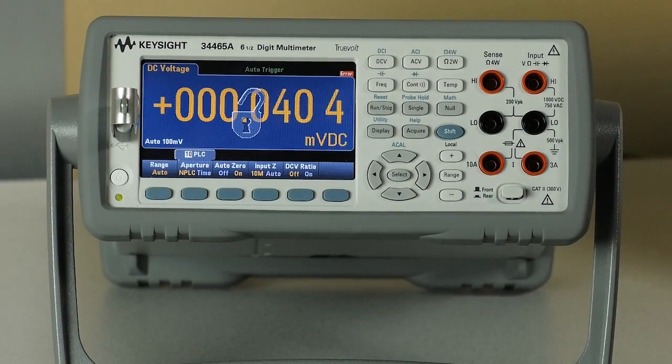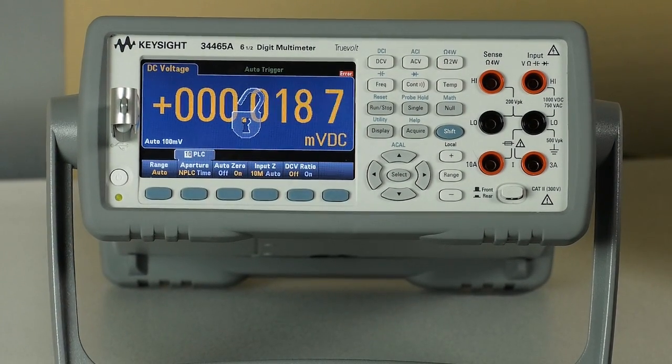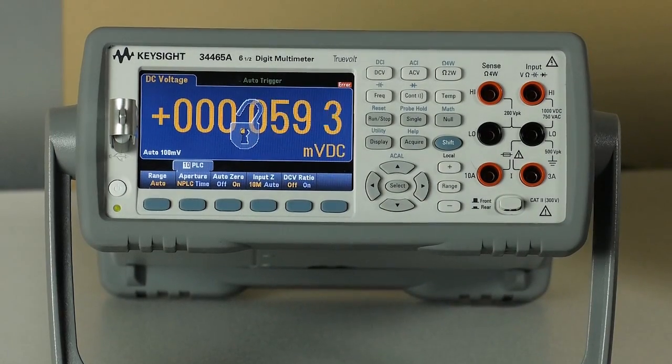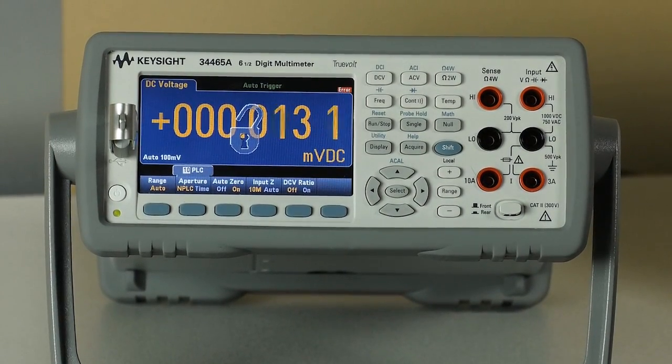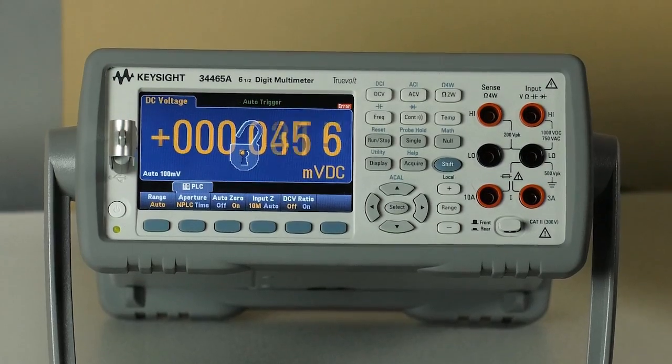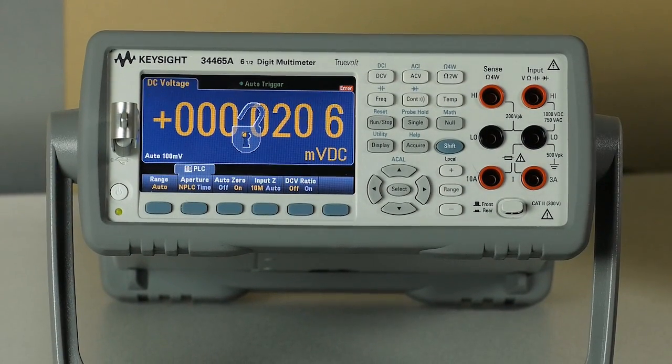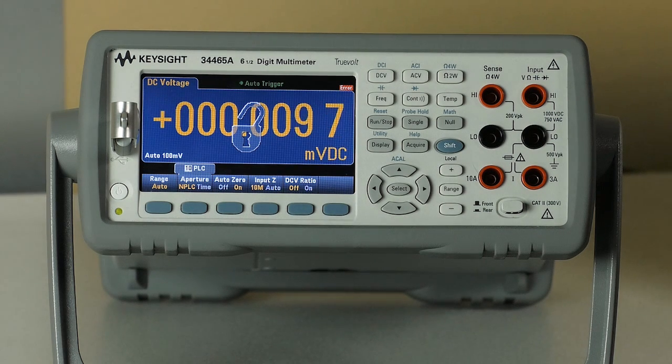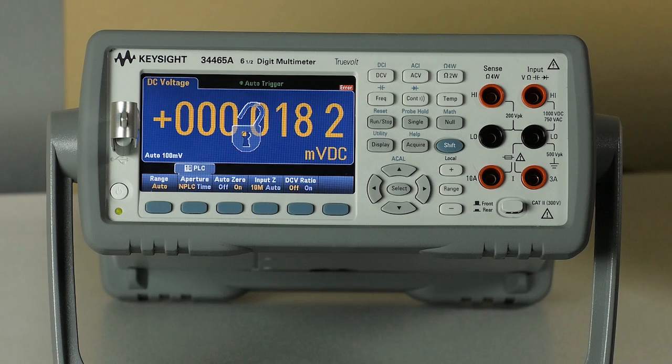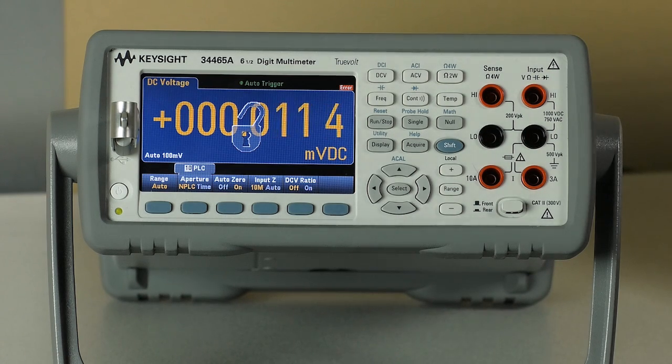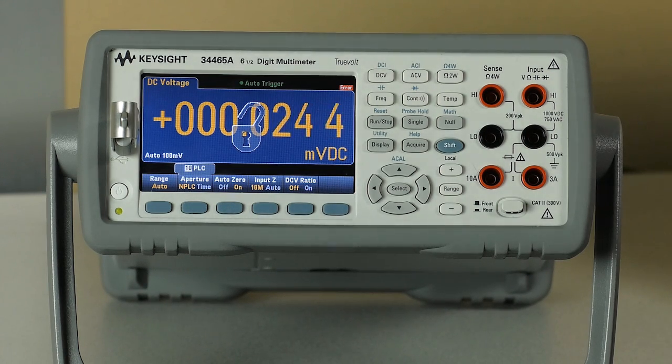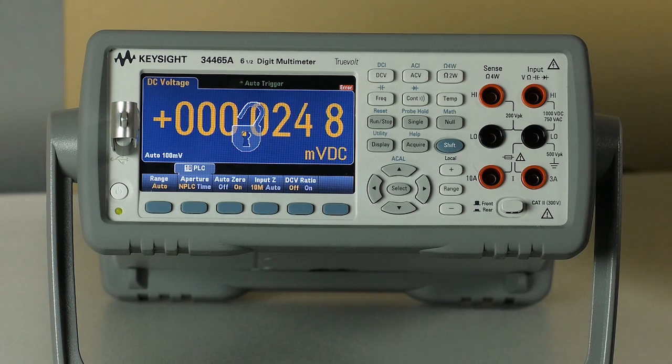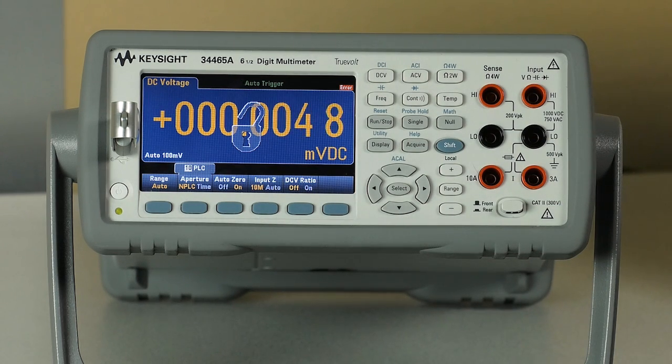One thing I do want to point out of particular importance is you may notice that there is an open lock on the front panel display. What that indicates is this particular instrument has the instrument security option or option SEC. Whenever doing a firmware update, programmatically or from the front panel, the instrument has to be unsecured in order for that to happen. So for the purposes of this video, we have went ahead and unlocked the instrument security allowing us to do the update.